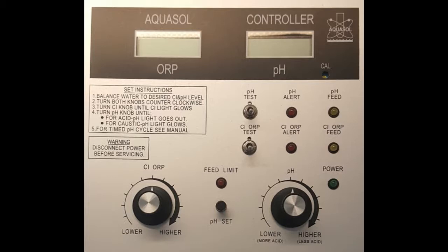if the pH alert, when is that going to illuminate? When is it going to go into pH alert? If you have a low pH, that'll activate and it won't allow any feed from the pH receptacle. So the range on the pH is the same for both boards. It's different on the ORP side. But that alert is going to go in when it's, is it 1 pH unit below, or is it a half pH unit below? I forget. That's going to be 1. So if they've got a set point of, say, negative 28 millivolts, then if the probe was reading positive 28 millivolts, it would go into alert. Right.